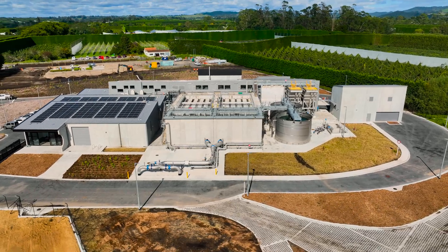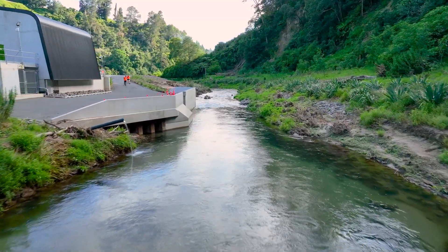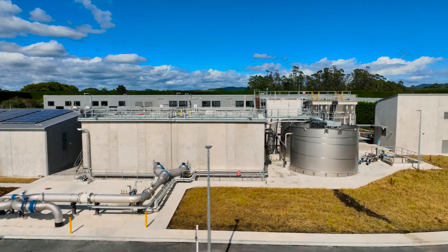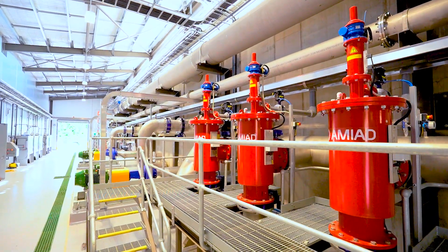The plant is a zero liquid discharge plant. What that means is that any drop of water we take from the intake from the Waiari stream is a really precious resource, so we don't want it to go to waste. We've recycled all the waste produced on site by the membrane and pre-treatment system, and it gets treated to a level where it's reintroduced into the feed water of the main plant.